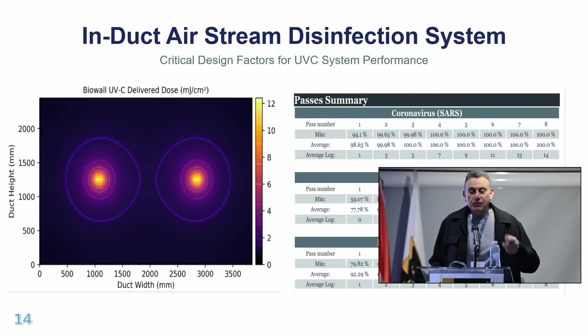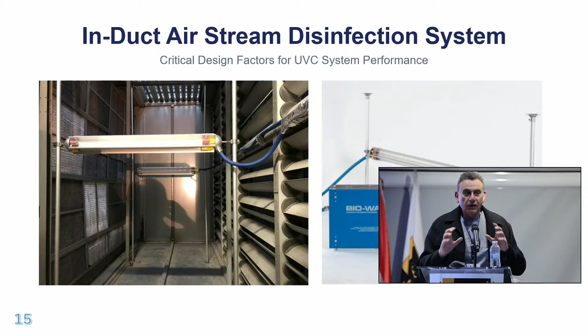So here is the actual installation. This is the mixing air plenum. We installed these 2 lights. They are actually a light battery. They're not only one light. They're a combination of 5 lights on each side. And these lights are controlled by this controller. And outside the air handling unit, you would see this, each battery of lights has a screen that shows these lights. It shows whether they are on or off. It shows the lifetime of the light, how many hours they've been on, and whether any light is damaged or not.